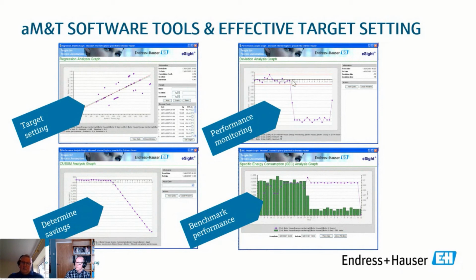Then if we implement something that's going to save energy—maybe a reburner, an economiser, oxygen trim, advanced combustion control, whatever we're doing—we might want to see a change in efficiency. So now we'd be consistently below that line, and that's what's happening here. We've improved the energy efficiency, consistently operating below this line of best fit, and we can set alarms around an optimum band we think is acceptable for that variation.